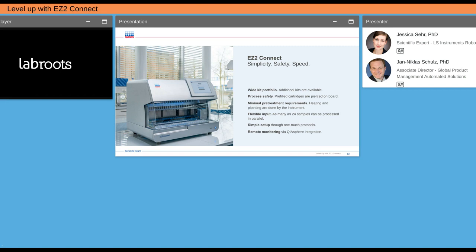This means if a run is finished, we have a very slow blinking. And if we have an error on the instrument, we have a bit faster blinking. And this means that even from far away, you can also see what the instrument status is all about.